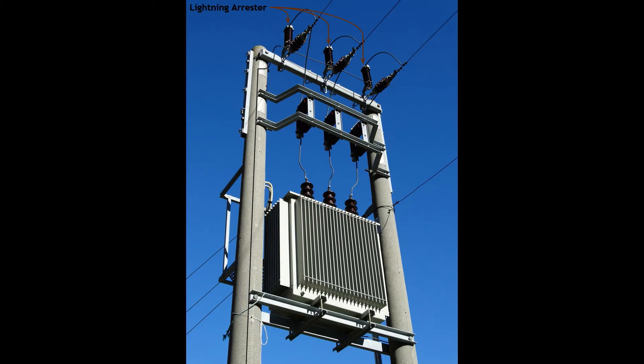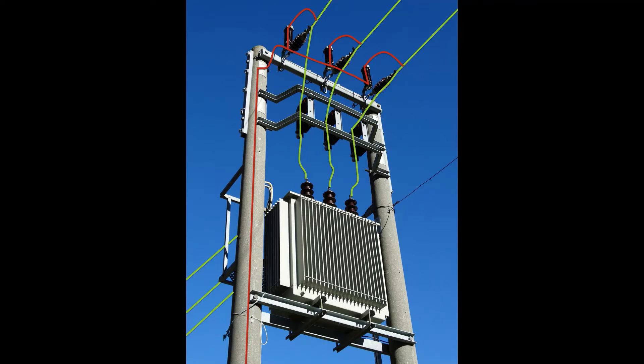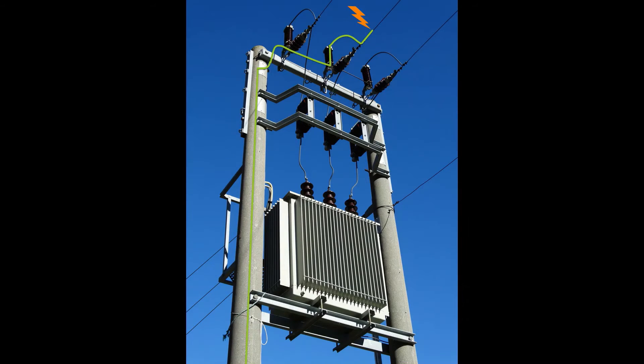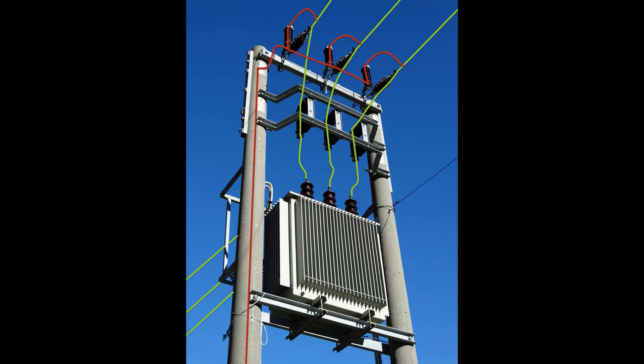A lightning arrester is much different than the lightning rod. At normal operating voltage the lightning arrester offers high impedance to the system voltage. When there is a system fault it senses overvoltage and the impedance reduces drastically. Once the surge energy is diverted to the ground the surge voltage reduces and the impedance of the surge arrester restores which means the lightning arrester regains its high impedance. This is a major difference between lightning arrester and lightning rod.